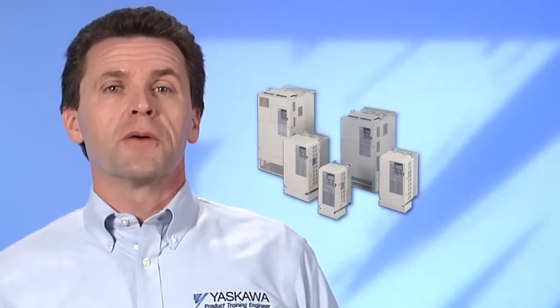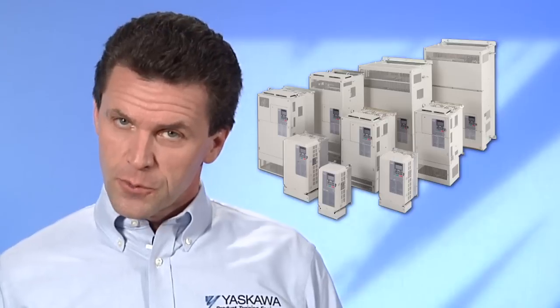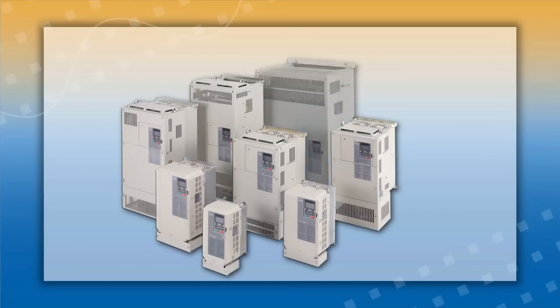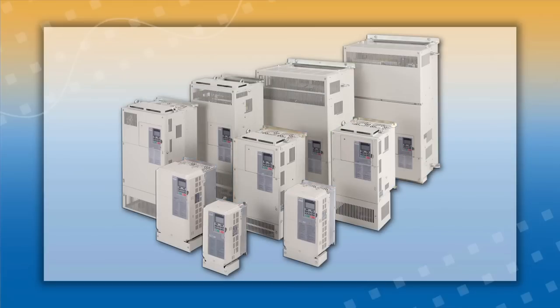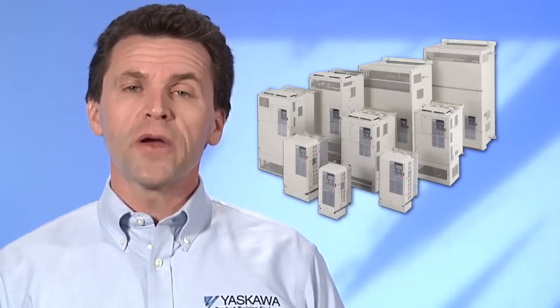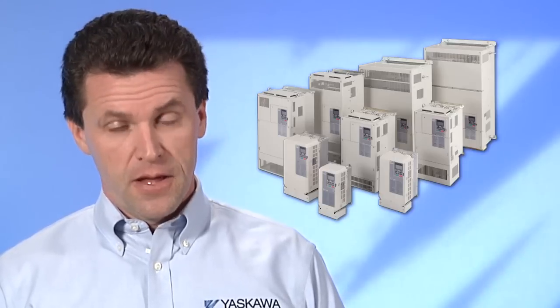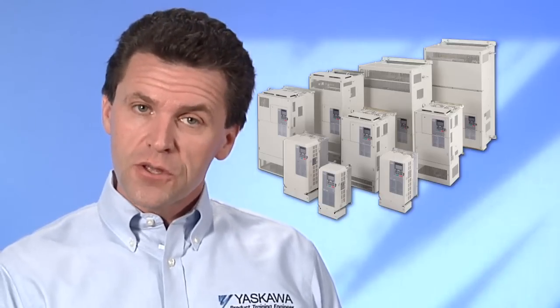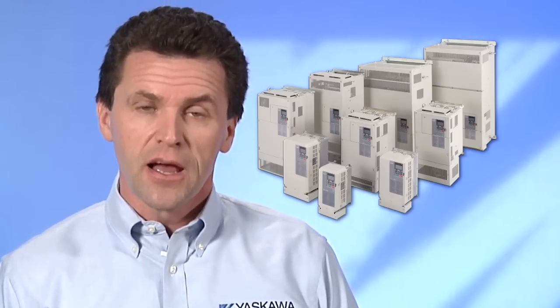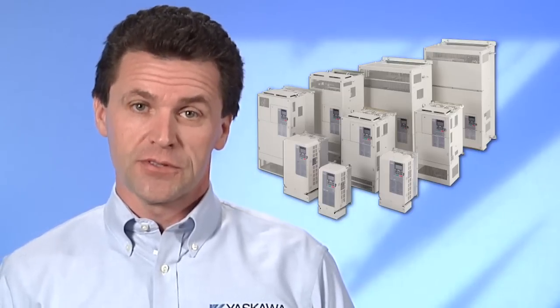Here's where the discussion comes around to the world of variable speed drives, also known as variable frequency drives, or VFDs. What kinds of harmonics do variable speed drives create? Well, the answer is it depends, especially based on the input rectifier scheme and the size relationship between the drive and the power source. Fortunately, there are things you can do to reduce current distortion on the power source, and these solutions are commonly much more cost-effective than increasing the power source's size.